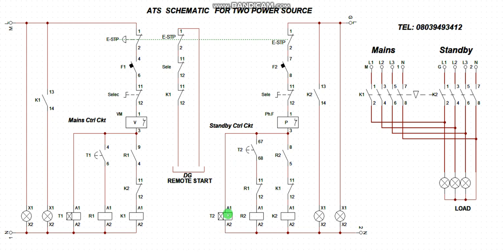When the preset time elapsed, like a few seconds, because once you put on the genset, you're expected to allow the gen to run for a few seconds before you engage a load. That is to enable the moving machineries and the oil to penetrate all the moving mechanisms before you now give a load to a generator. That is the right principle of using a generating set.